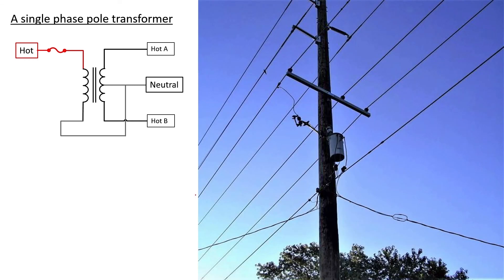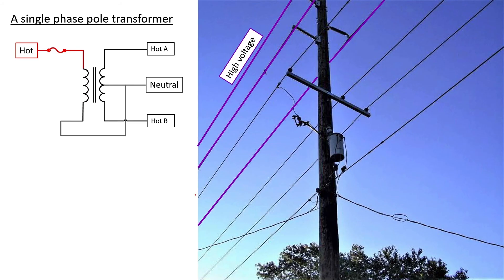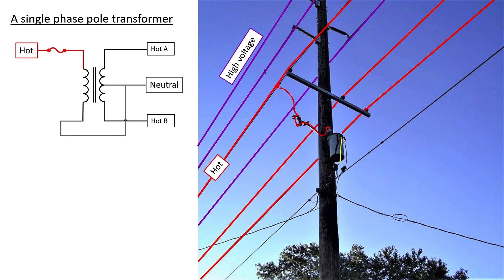Let's take a look at a pole that has even more electrical lines. A single utility pole can have multiple voltages — higher voltages up at the top with larger insulators, and lower voltages further down. The transformer connects to one of the three phases via a fuse and primary bushing. On the secondary side, there are three connections: a neutral coming out of the middle and two hot wires on either side. The neutral is tied to ground and earthed in multiple locations throughout the network in order to provide network stability.